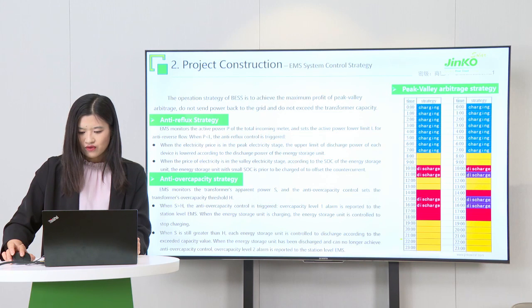The operation strategy of the Dongguan Xiaodong New Energy Company Battery Energy Storage System project is to achieve the maximum profit of peak-valley arbitrage, not send power back to the grid and not exceed the transformer capacity, namely the anti-reflux strategy and the anti-overcapacity strategy. For the anti-reflux strategy, the EMS monitors the active power P of the total incoming meter and sets the active power lower limit L for anti-reverse flow. When P is less than L, the anti-reflux control is triggered.